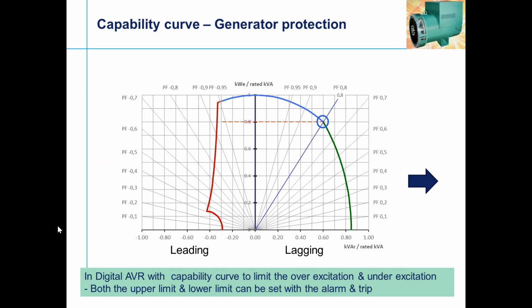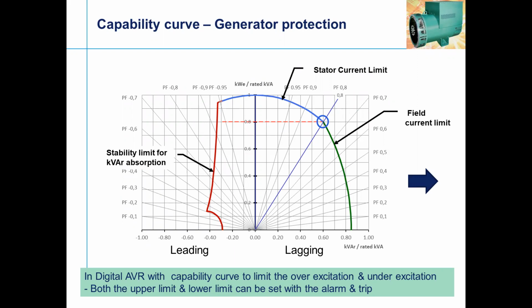So on the left hand side, you can see I was just talking about the voltage following the current. It becomes leading, and when the current follows the voltage, again it's lag. So in the intermediate, you can see the center line, which is the unity power factor. A generator capability curve talks about the three-point settings. You have the stator current limit. Again, you have the field current limit, which I was talking about as the excitation current. And again, we have the stability kVAr limit, that means reactive power absorption on the generator.